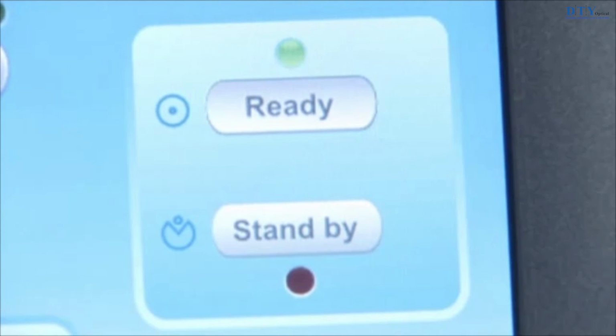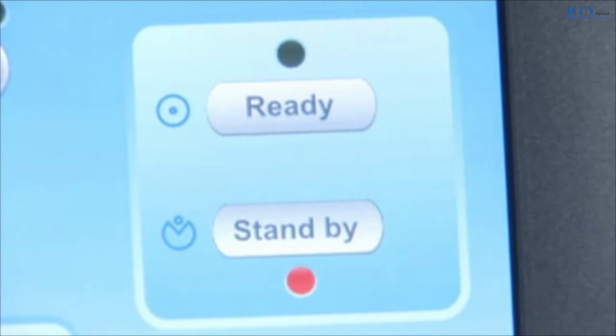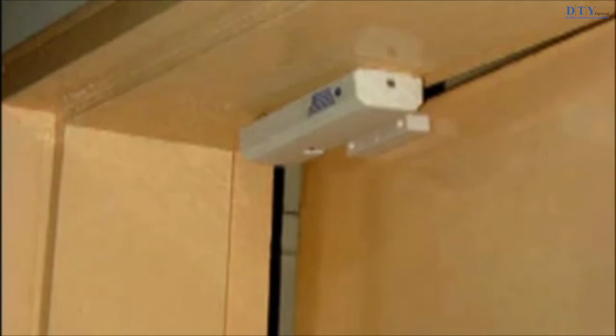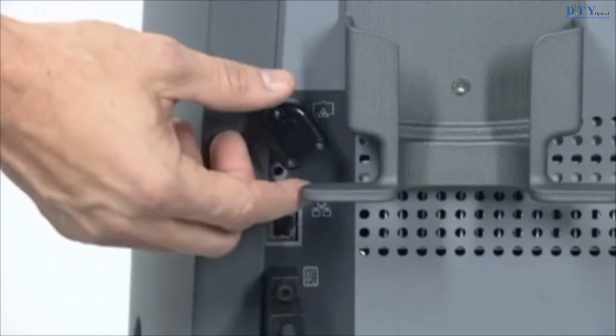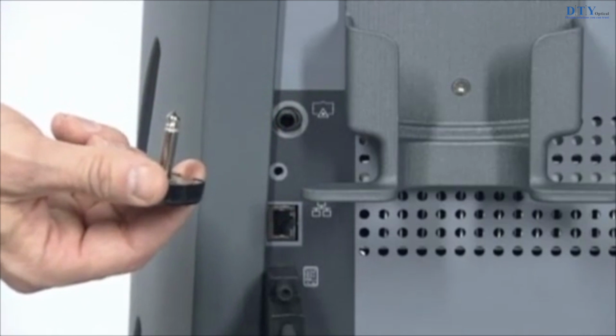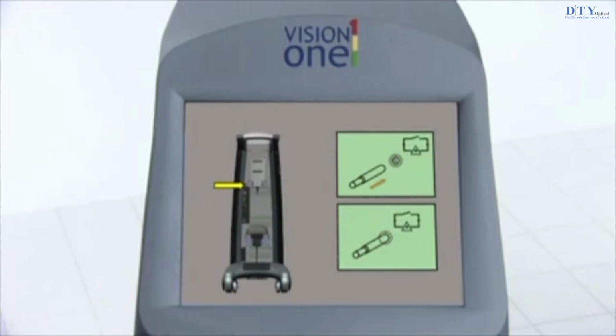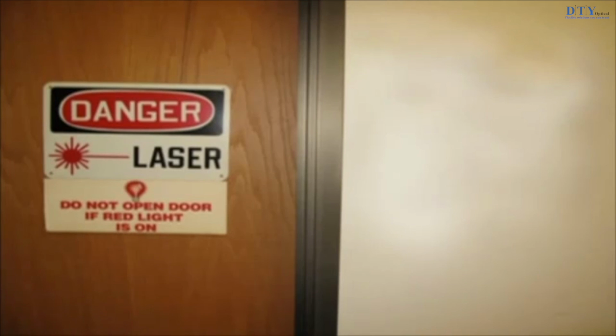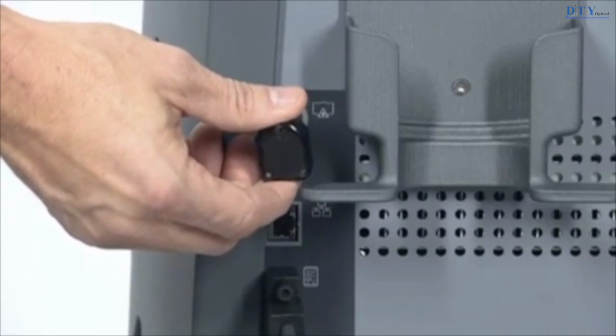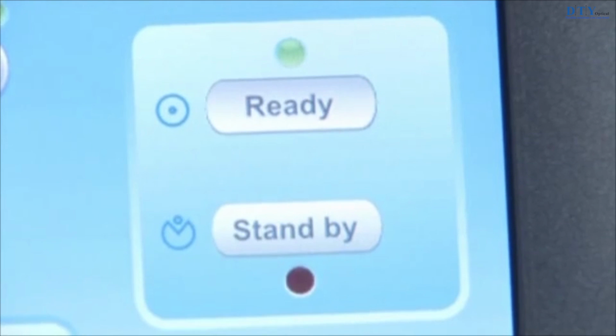When using an external door interlock, the laser automatically disables and returns to standby mode if the treatment door is opened or the interlock plug is removed. The following illustration displays on the control screen. To resume treatment, close the treatment room door or reinsert the interlock plug, and press the Ready button.